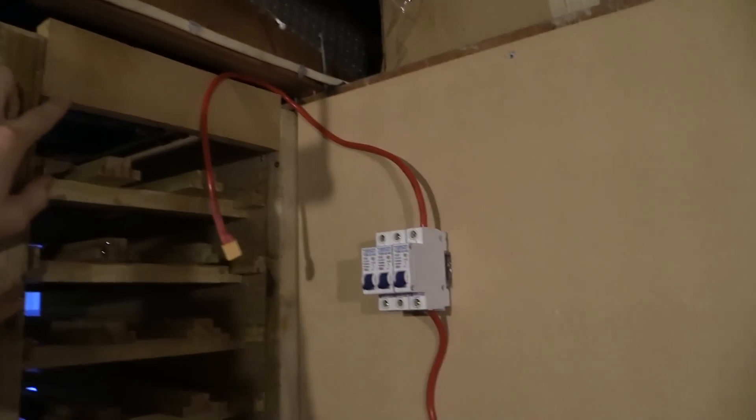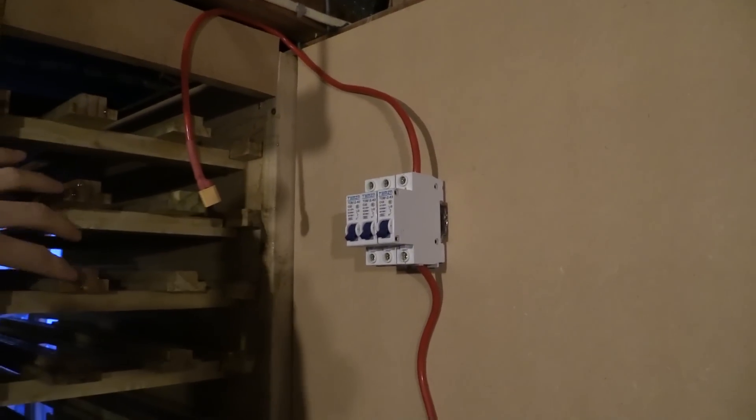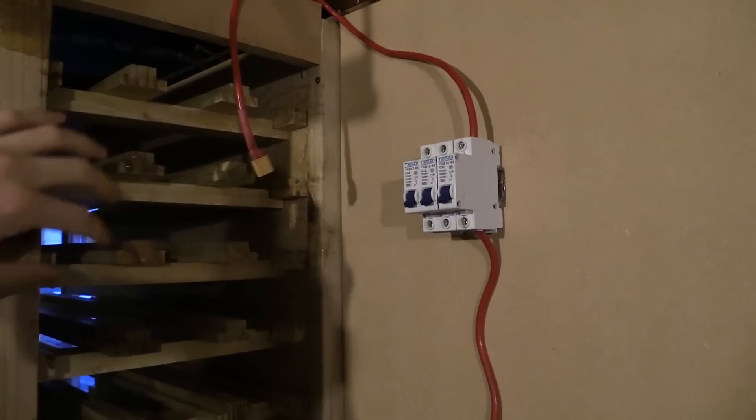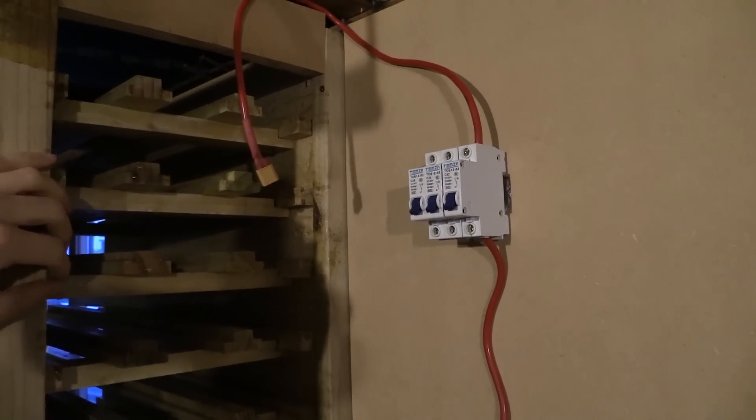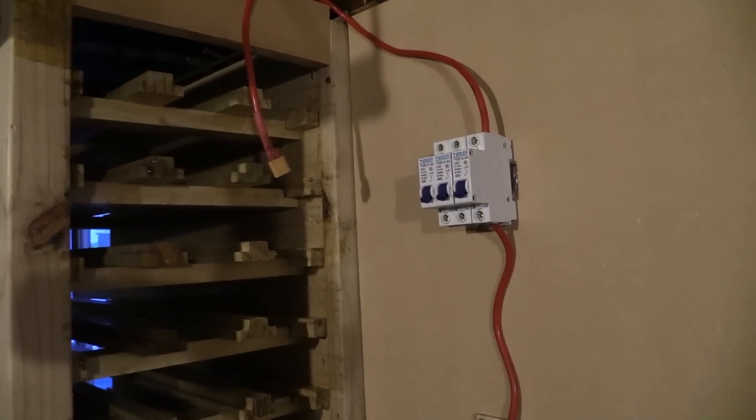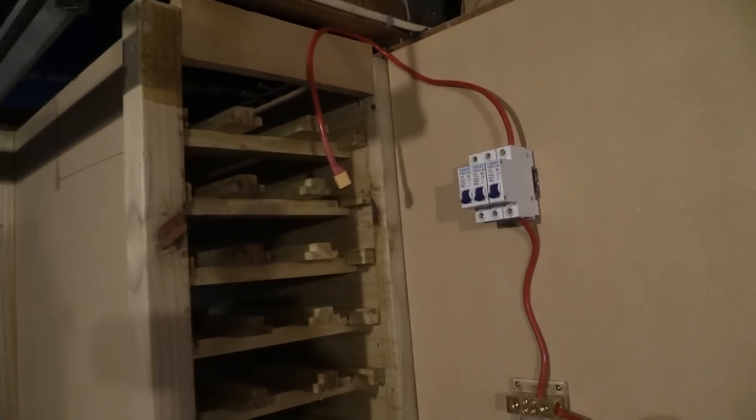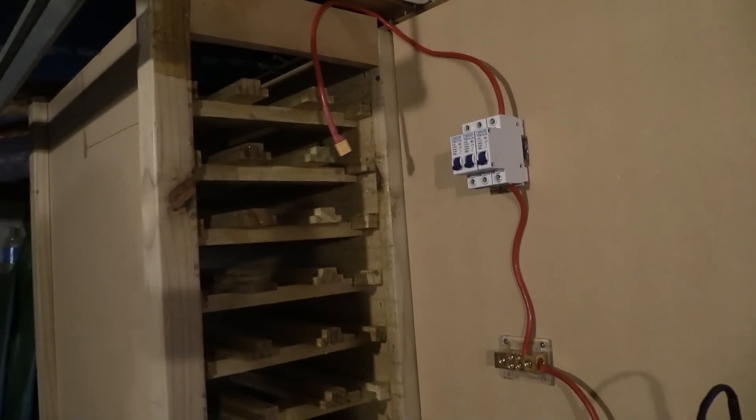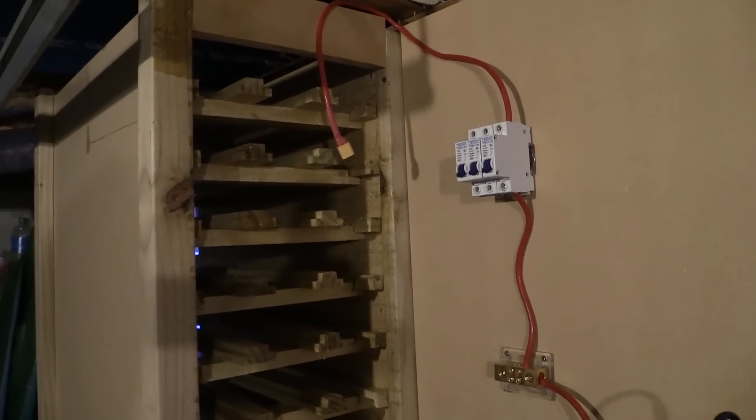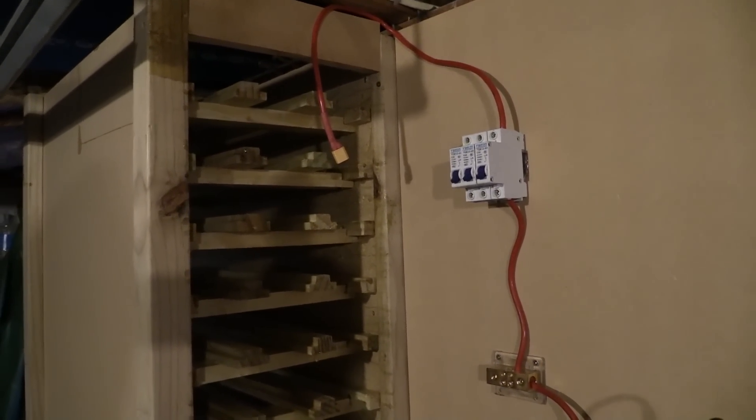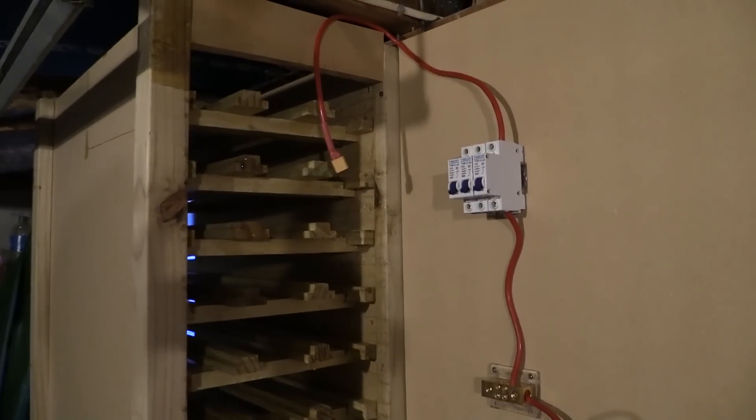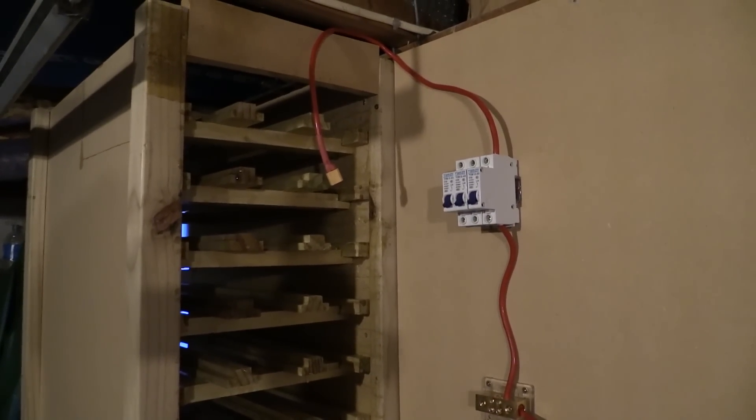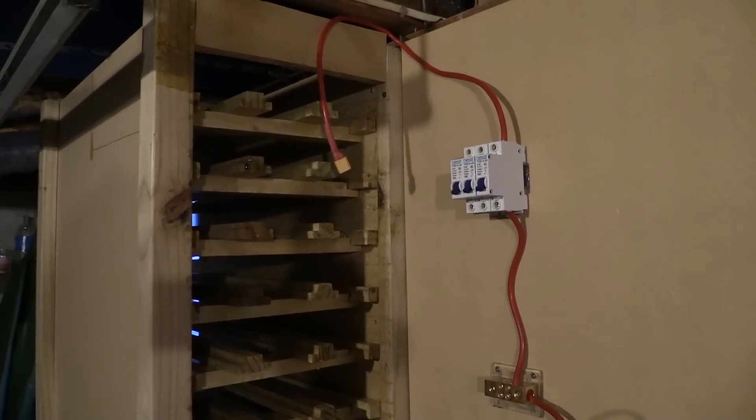The reason I did that is so that the cable length per bank of five kilowatts doesn't vary too much. Watching a couple of YouTube videos, it's suggested that when you're connecting packs of series into parallel, which is pretty much what we're doing, it's best to keep the wire length the same between all the packs.